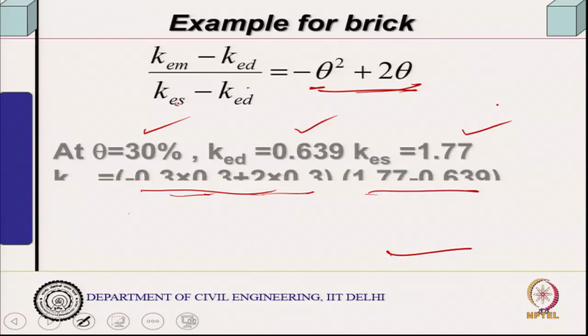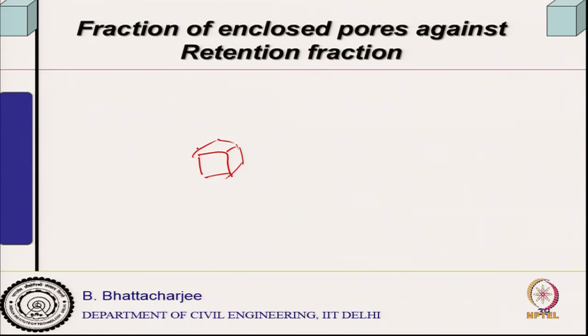How? Essentially you have a small sample which is first evacuated, and then submerged into mercury at atmospheric pressure. So, evacuated to let us say 1 micron level or such level of evacuation, then submerged into water, I mean the mercury. Mercury will penetrate at atmospheric pressure, then apply more pressure, because mercury is a non-wetting liquid.